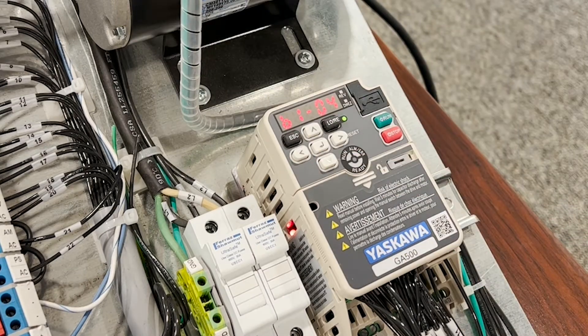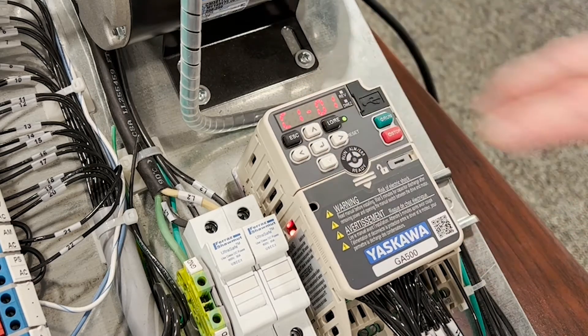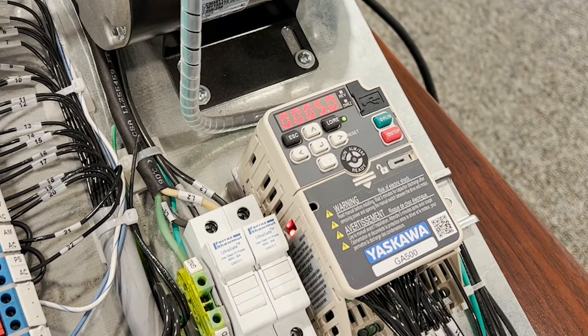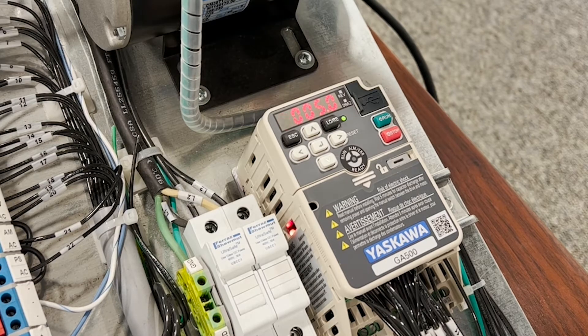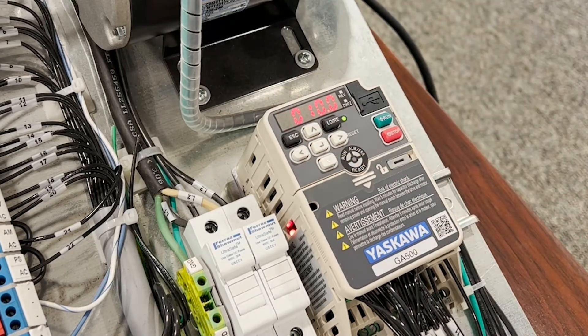Now we need to worry about our acceleration and deceleration time. Our acceleration time is parameter C1-01. I have it set to 5 seconds; from the factory it comes as 10 seconds. This means our motor will go from 0 to 60 Hertz in 5 seconds. The deceleration parameter is C1-02, which factory defaults at 10 seconds as well, and we're going to leave it there.